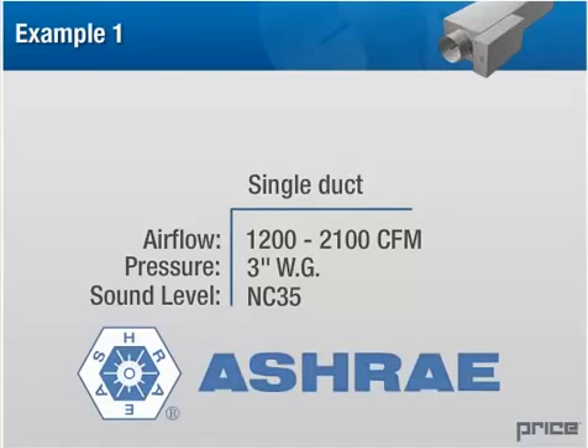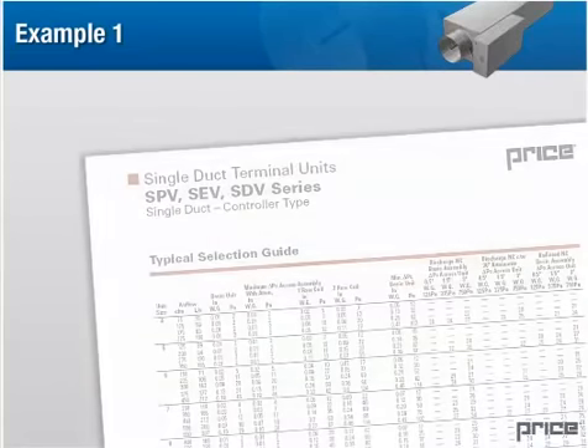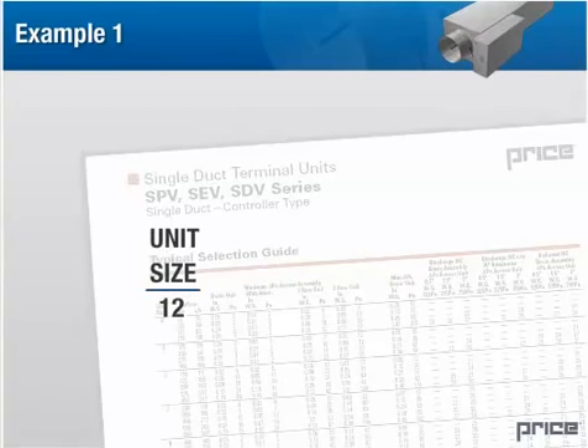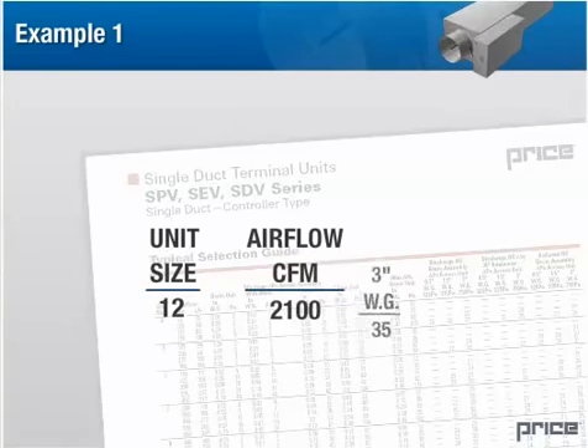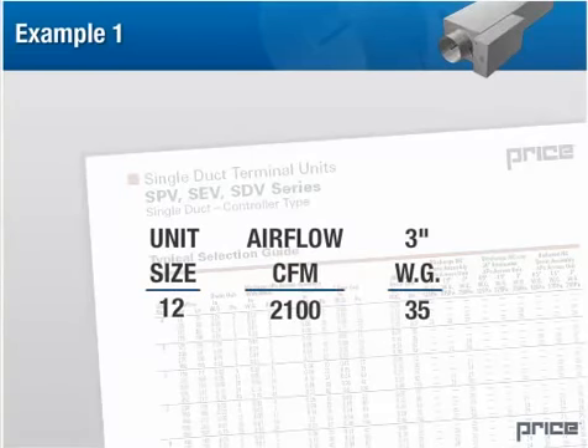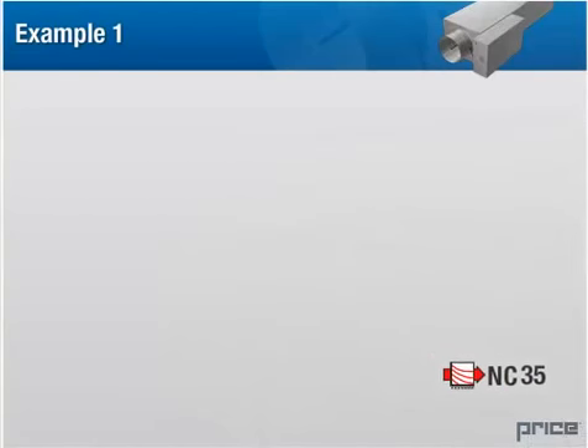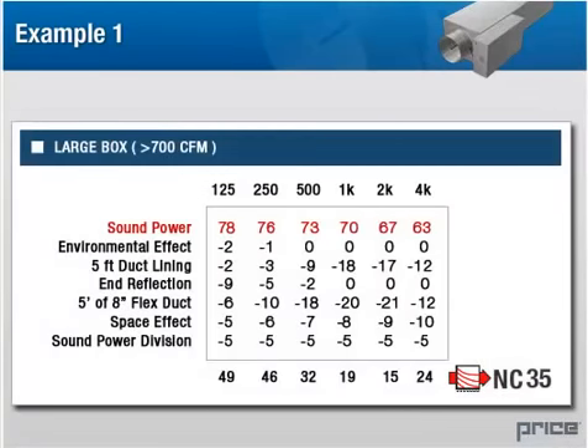By skimming the terminal's catalog, a selection of a size 12 SDV is within the range of flows and just meeting the NC criterion at its maximum capacity with a discharge NC level of 35. Now we have to remember that these NC levels have been based on the standard deductions provided by ARI 885. If we look at these values in detail, there may be one or more items that do not match the actual system used in this example.